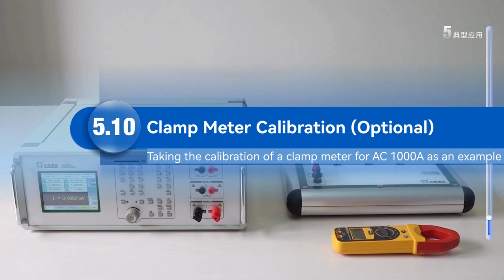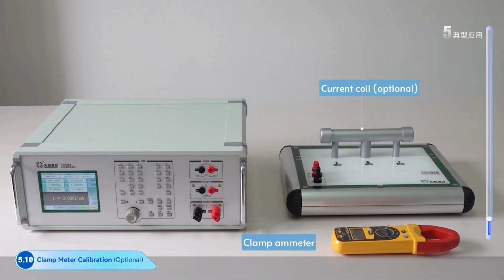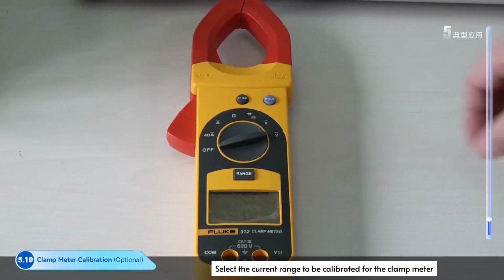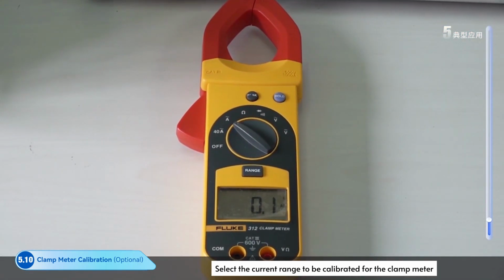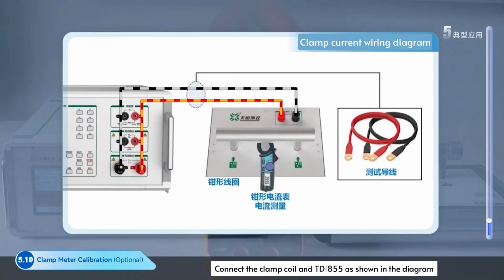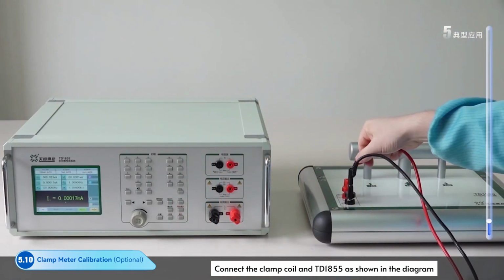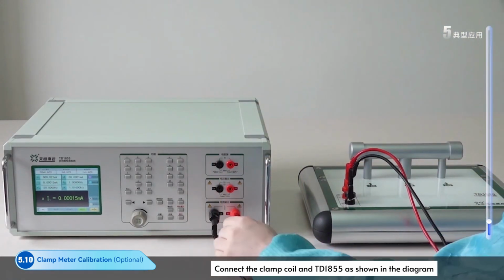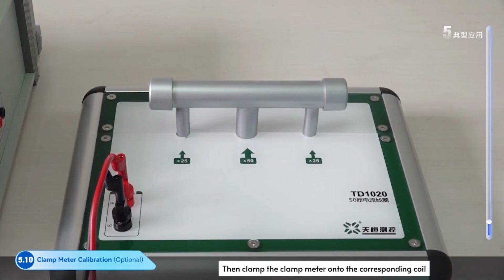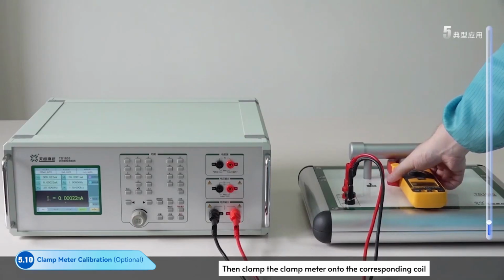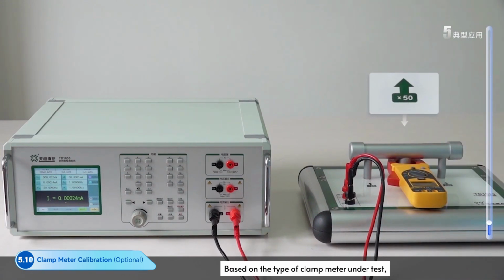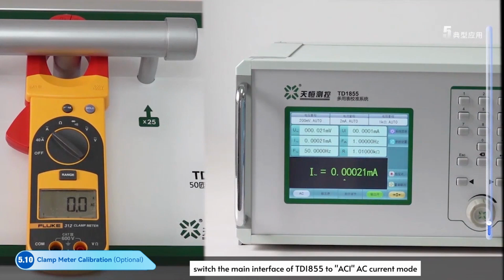Part 10. Clamp meter calibration. Optional function. Select the current range to be calibrated for the clamp meter. Connect the clamp coil and TD1855 as shown in the diagram. Then clamp the clamp meter onto the corresponding coil. Based on the type of clamp meter under test, switch TD1855 to ACI AC current mode.